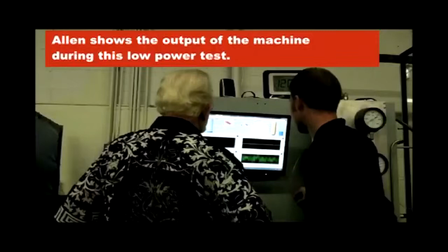That's my thermocouple inside there, that's the top one. The coolant is what the temperature is inside this — that coolant reading is actually up there, so that's reading the temperature up top. It's 108 degrees up there. You've got my pressure right here: it's 284, this is 289. So they're within a tiny percentage point of each other.